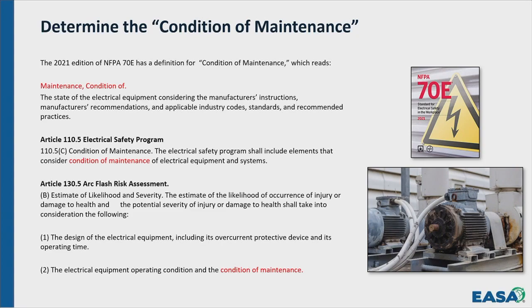You're factoring in everything the manufacturer and industry standards say—whether that's Article 100, the 70B, NETA's testing standards, or the manufacturer's recommendations. What they're saying is that the electrical worker in the field has to understand the condition of maintenance before they interact with that piece of equipment. The standards are pushing us to do that from a safety standpoint, so that as an electrical worker, when we walk up to something, we have to understand what condition of maintenance it's in.